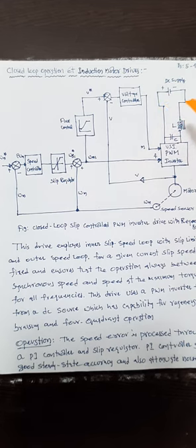So you see here, this is the closed loop operation of a VSI fed induction motor drive using a PWM technique. This drive is capable of operating in the regenerative mode also. When the VSI is operated in the PWM inverter mode, no extra arrangement is required. A constant DC supply is directly changed into variable voltage with the help of the PWM inverter, so variable voltage is obtained with this technique. Now variable frequency is required for us.